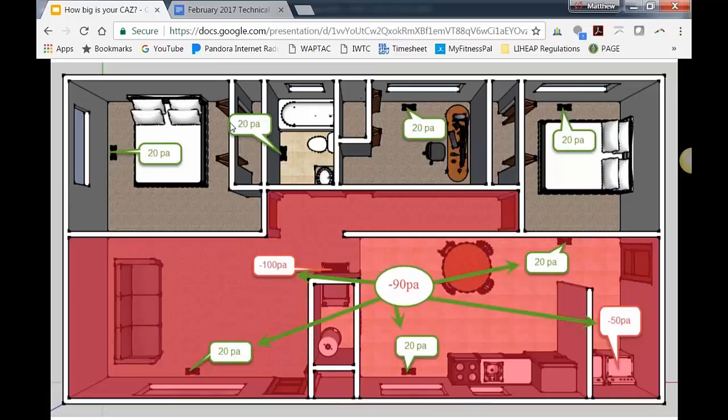So what else do we need to worry about? The auditor found the house in this condition, but now we start working on it. What are some of the things that we can do during the process that could totally throw a wrench in all of this? Add fans. Yeah, the big one is the fan. I had a house that we went into to do a QCI on it, and it was failing worst case draft.